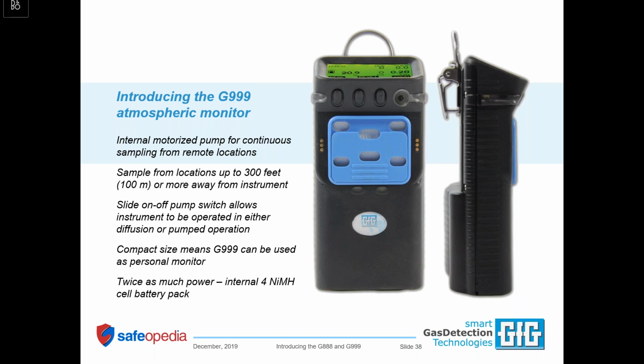The pump is powerful — a diaphragm pump easily capable of drawing a sample from 300 feet away from the instrument. It includes a shutter switch that allows you to turn the pump on or off when you don't need to actively draw a sample from a remote location. So you can do your pre-entry checks using the pump, then turn it off afterward. You're not wasting battery power on the pump when it's not needed.